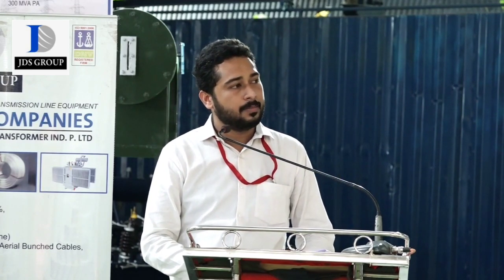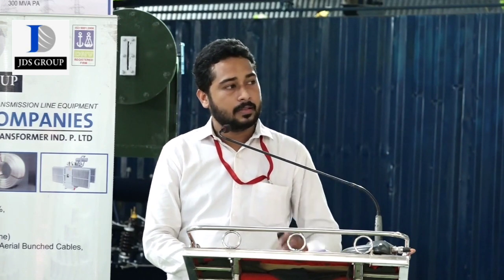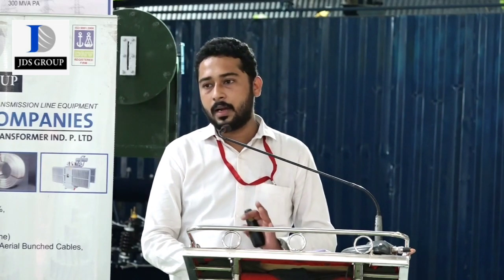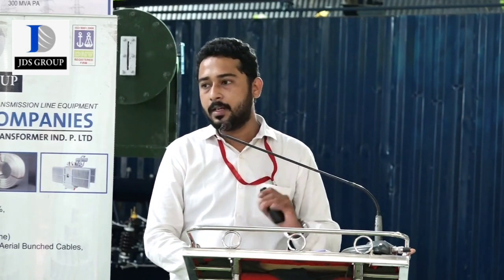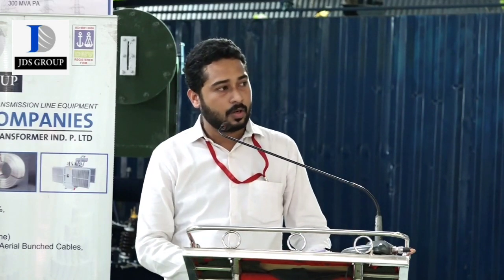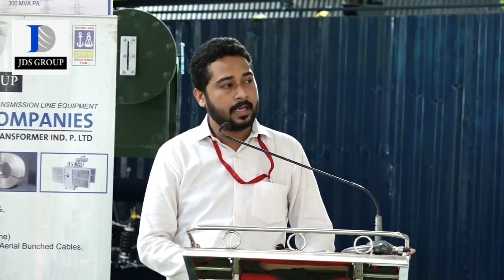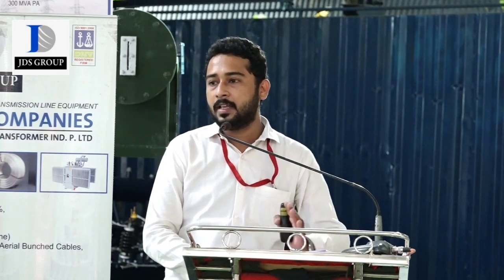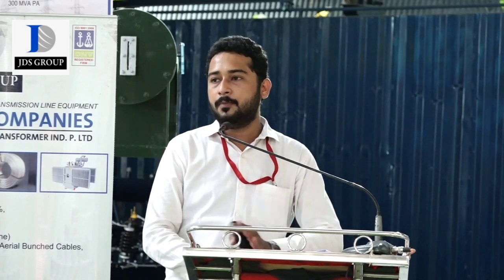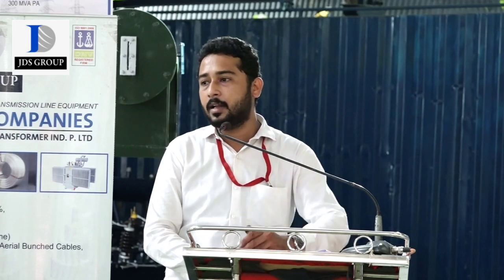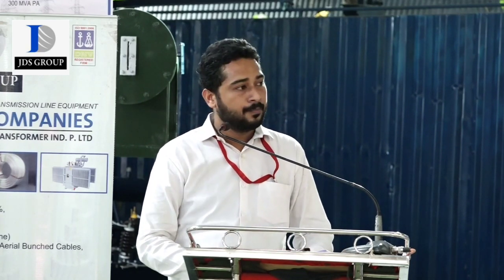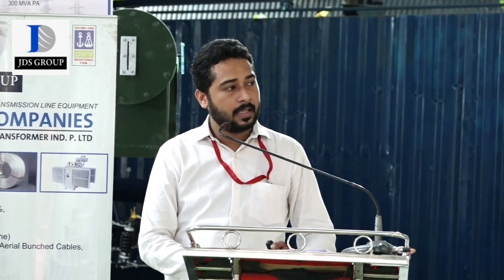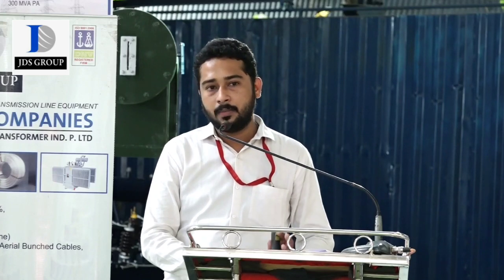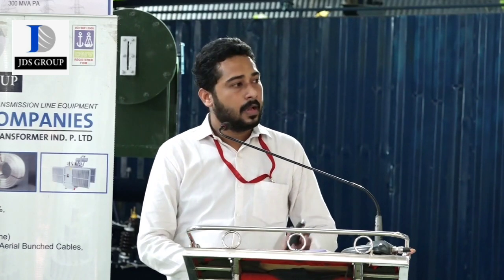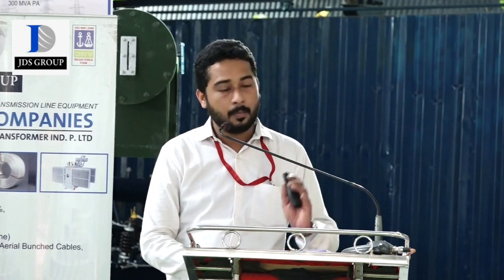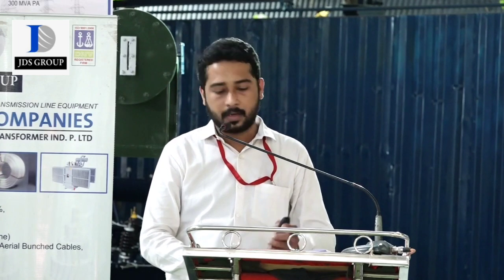Design considerations for an earthing system. The first is serviceability: it should be a cost effective product, feasible for everyone's pocket. Second is the evaluation of performance continuity in diminishing of current carrying capacity, meaning its life: from the time it is installed till the end of its life, how much it will dissipate. Third is the corrosion environment, whether there is any kind of soil or environmental factor, corrosion should be less. And the last is a study of failure frequency of the material, that is cast iron, with other materials which are available in the market.